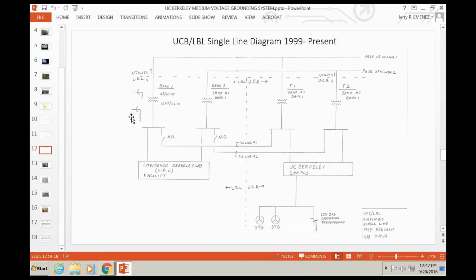Yeah, so they did not have any problem with the grounding resistor here on the secondary, but they did dictate that the primaries had to be a grounded Y configuration. We had to run our design by them, and they certainly could critique it, and they could tell us what was allowable and what was not. But I'm told that because of this cogen plant down here, all of these transformers had to have a grounded Y primary on them. I haven't been too involved with picking out transformers before, but you might normally pick out a delta winding for this 115 kV, but PG&E insisted on a grounded Y, so that part they did have influence on us, and they told us what they wanted, and we had to go with it. I'm sure they've thought it through, and it's worked.